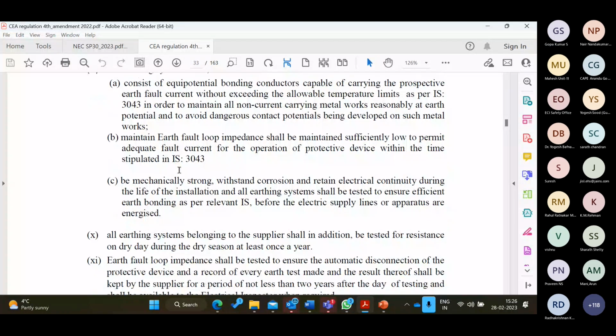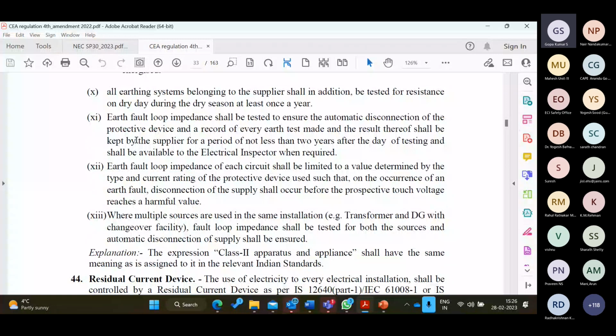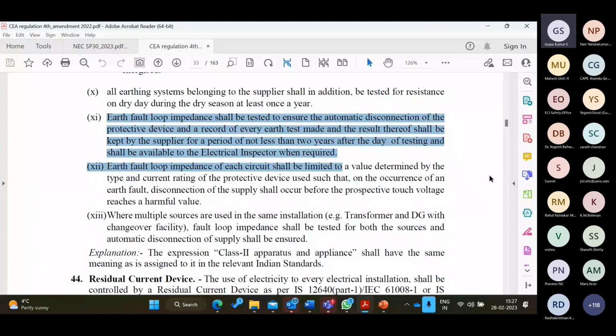Now, regulation number 43, sub-regulation number 11. Earth fault loop impedance shall be tested to ensure the automatic disconnection of the protective device, and a record of every earth test may be made and the result thereof shall be kept by the supplier. Please note, this regulation is applicable for generation, transmission, distribution and usage. So this regulation is saying that the supplier shall keep the record of fault loop impedance.